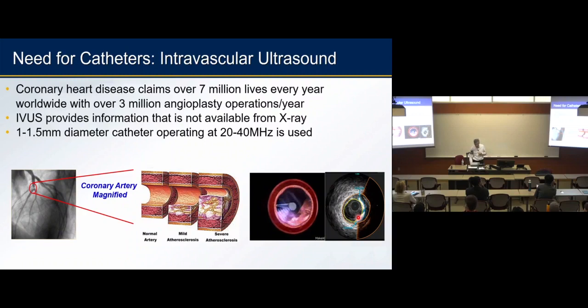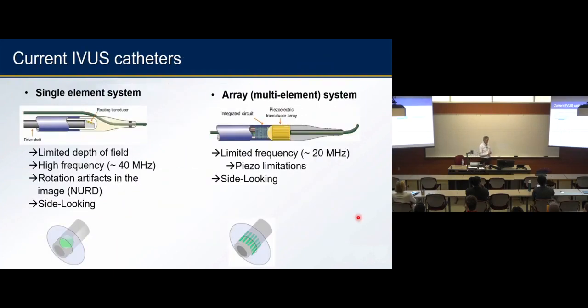Again, for these things, you're looking at 1 to 1.5 millimeter diameter catheters in the 20 to 40 megahertz range. You want those high frequencies because resolution increases with frequency. Wavelength comes down, so you want to go higher, but you cannot do that from outside because ultrasound gets attenuated very fast at high frequency. So you cannot just put a probe outside the body. That's why you have to go inside, because you only have maybe 2 to 3 millimeters of imaging depth.